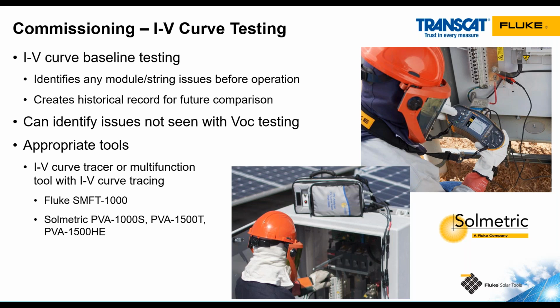The PVA 1500T model, when the efficiency rating of the module is above 19%, the current rating drops from 30 amps down to 10. So that's to be able to deal with that inrush current and not overheat. The PVA 1500HE2 model is specifically designed for working with high efficiency modules. It can test up to the full 30 amp rating no matter what the efficiency of the module. So if you're working with high efficiency modules, that 1500HE2 model is really an ideal choice.